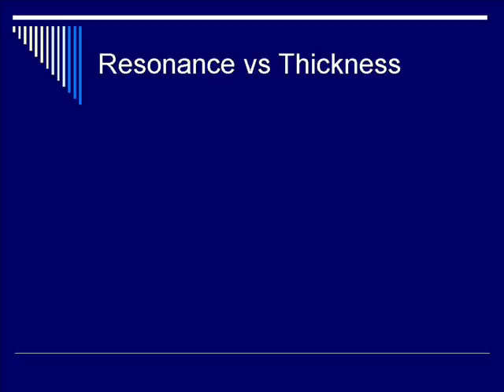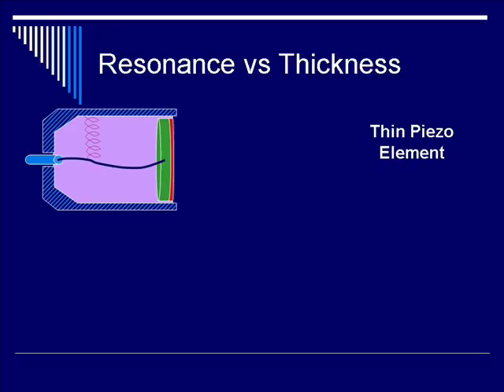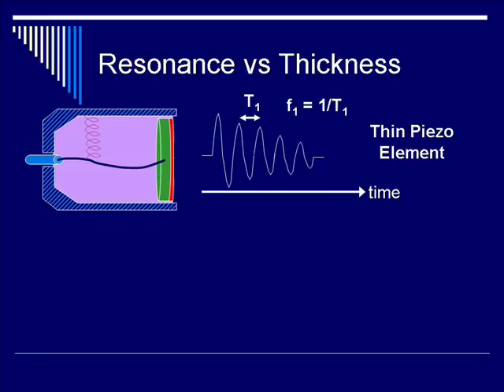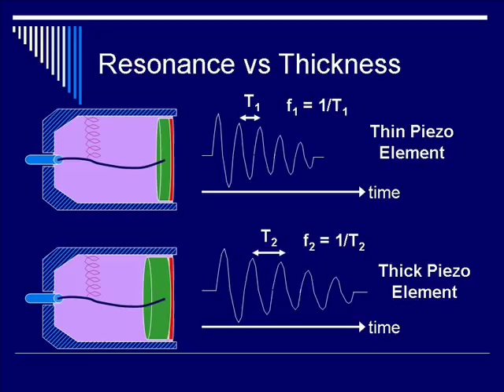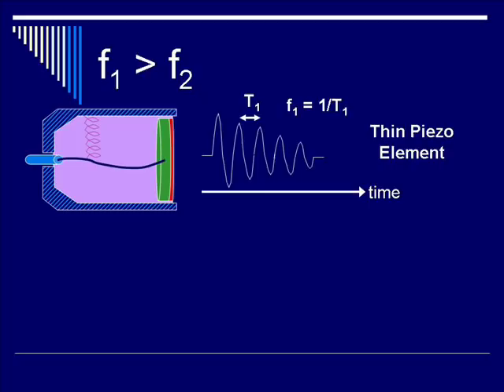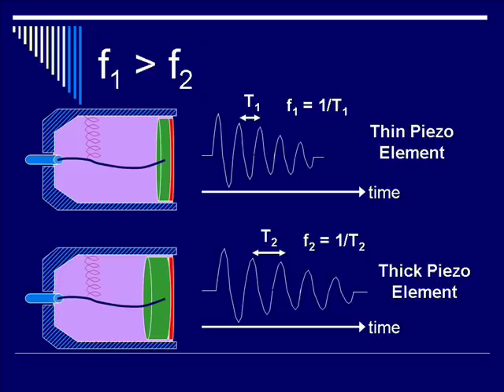Looking at resonance versus thickness: a transducer with a thin piezoelectric element has a characteristic acoustic output with period T1, while a thick piezoelectric element has a characteristic output with period T2. Since T2 is larger than T1, frequency F1 is greater than F2. Therefore, the higher frequency is associated with the thinner piezoelectric element, and the lower frequency with the thicker element.